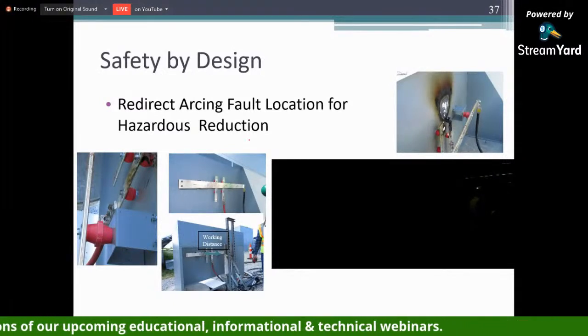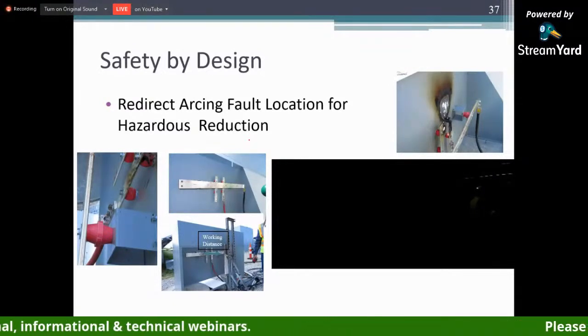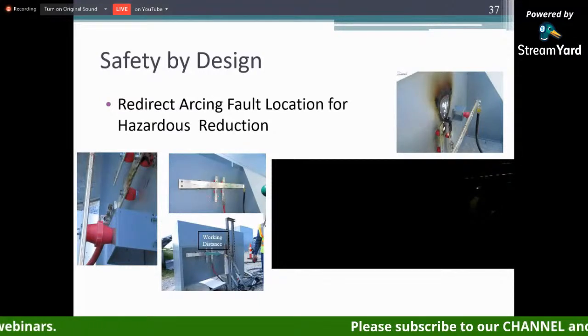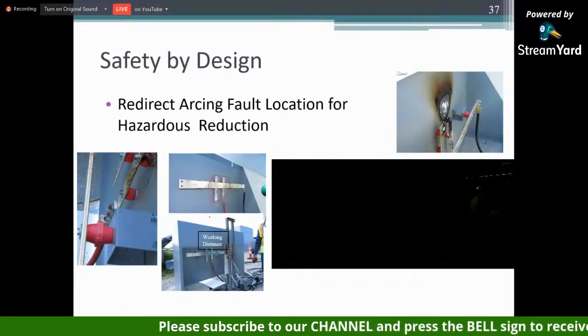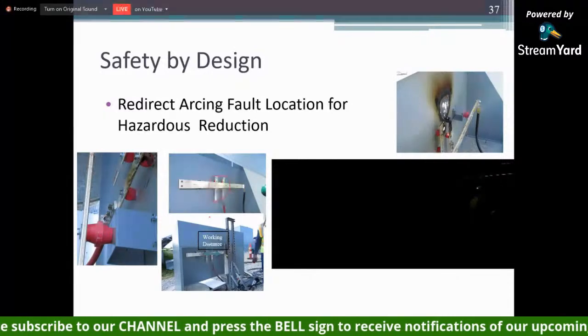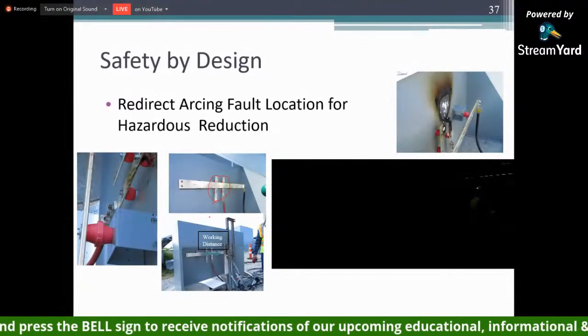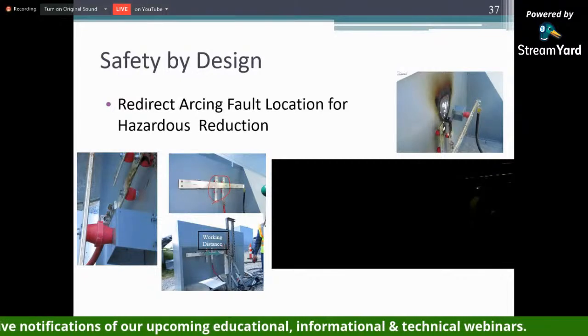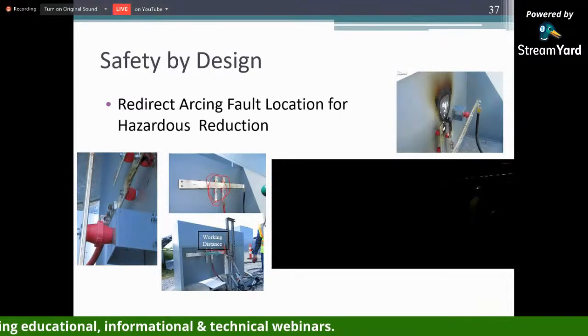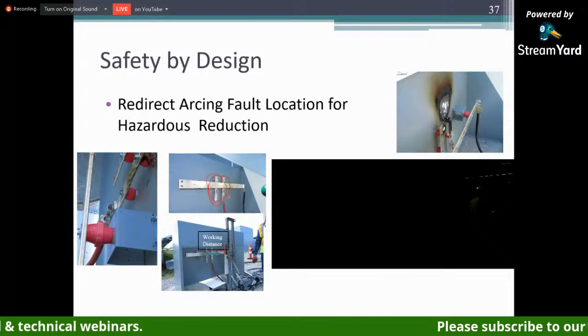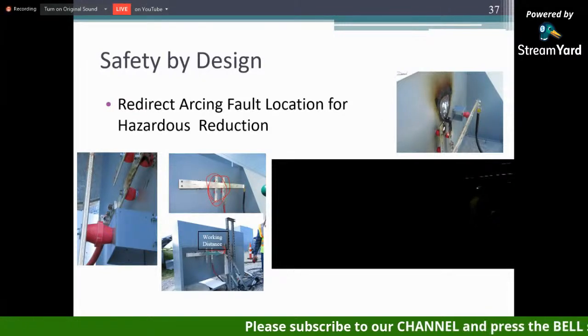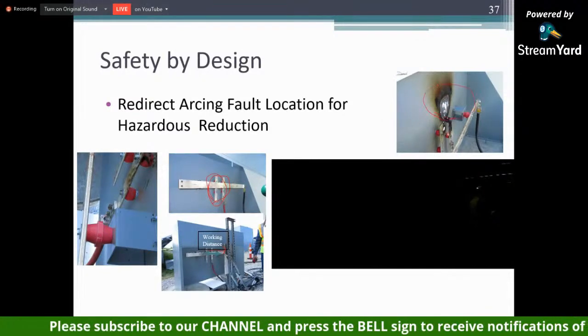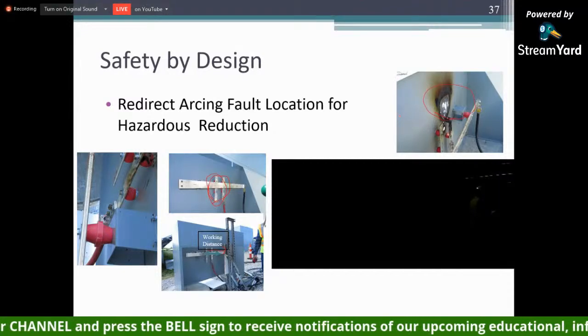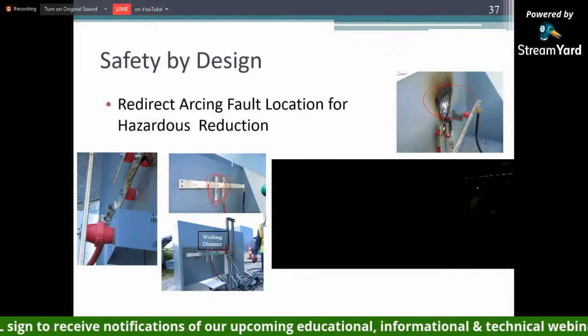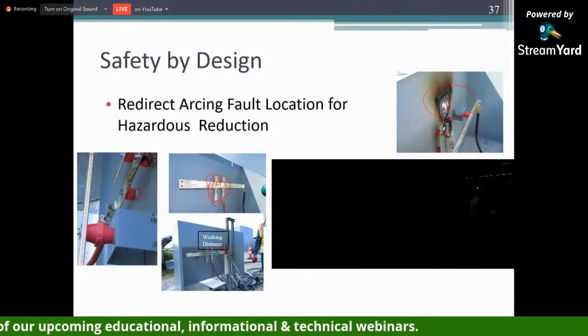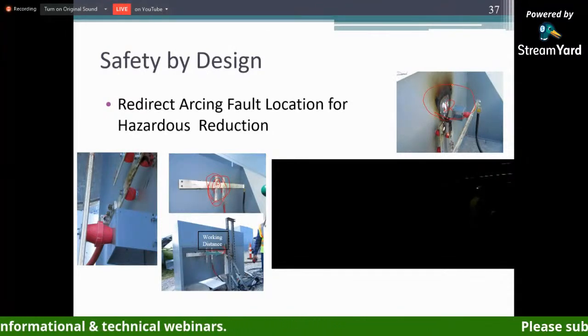And the other one is, when you try to design a system, we always say safety by design. For this particular case, the initiation point is here. When you design it, you try to create - that is basically the working distance, people are working on this area, and it caused the fault. So then you try to create a certain area that becomes a weak point, so the arc transfers, instead of happening here, it happens here - it transfers over so it doesn't hurt people.